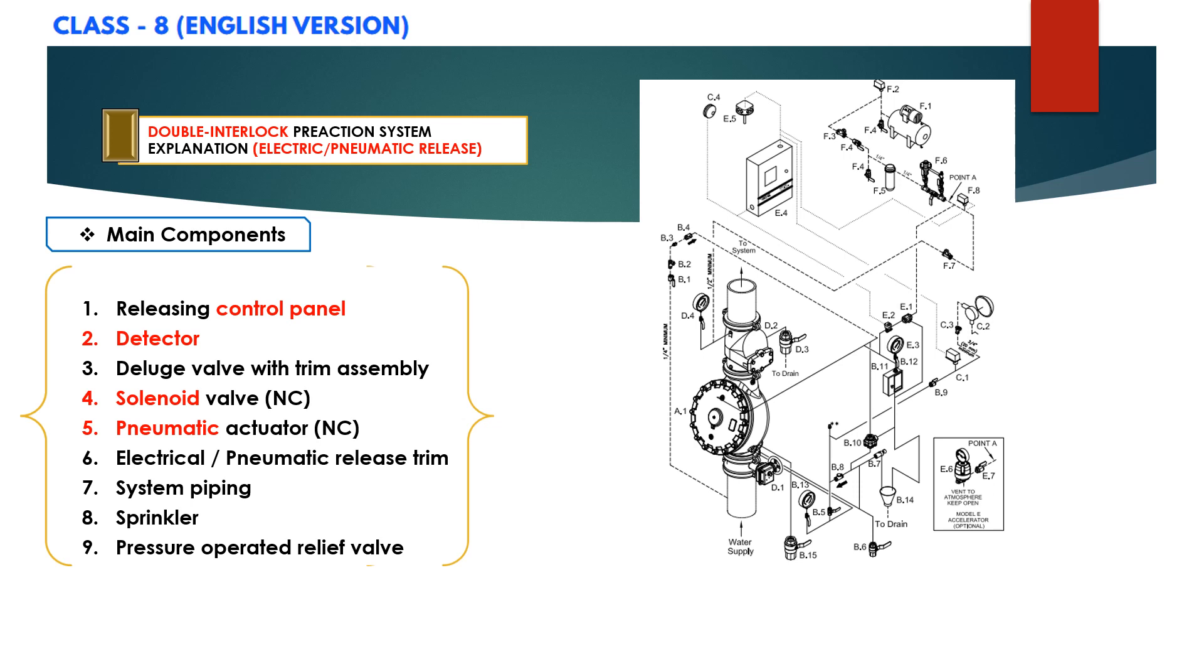These systems utilize a deluge valve controlled by a pneumatic actuator E1, normally held closed by supervisory pressure maintained in the automatic sprinkler system and a normally closed electric solenoid valve E2 controlled by an approved system control panel with compatible detection system.